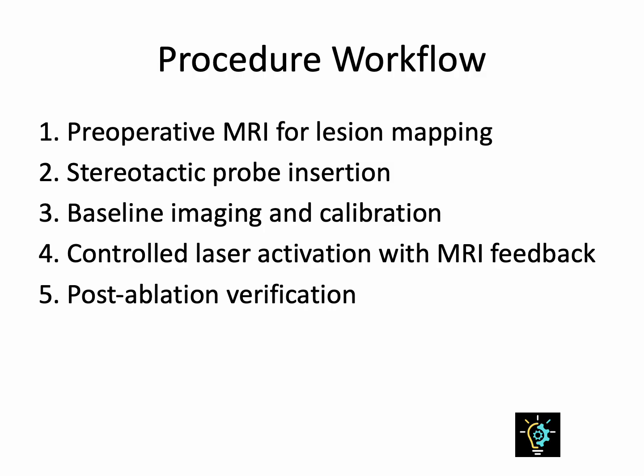From an engineering viewpoint, LiTT is a carefully choreographed process. Pre-operative MRI defines the target and trajectory. The surgeon or robot guides the probe into position under image navigation. Calibration ensures alignment between physical and digital coordinates. The laser system then delivers energy in controlled pulses, while MRI thermometry verifies safe heat distribution. After the ablation phase, imaging confirms lesion containment and absence of collateral damage. Each stage depends on hardware communication fidelity, imaging accuracy, and precise actuation of mechanical components.